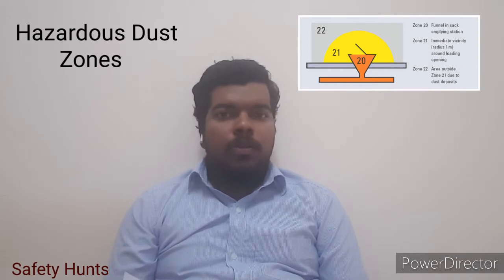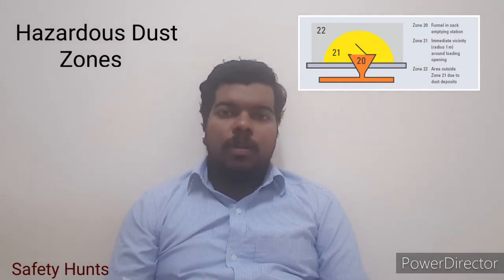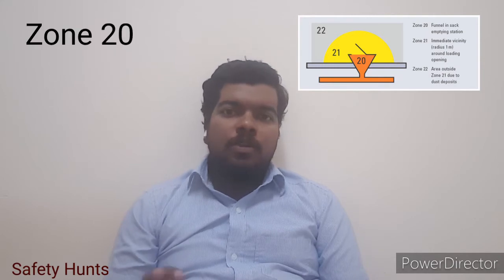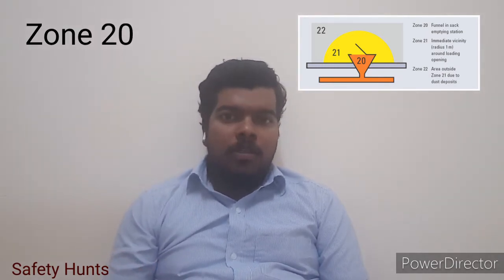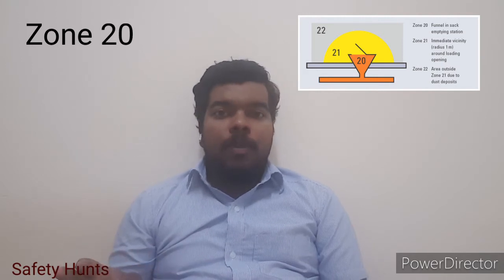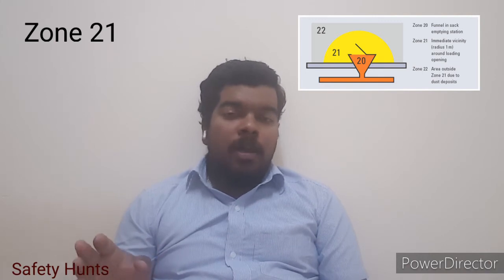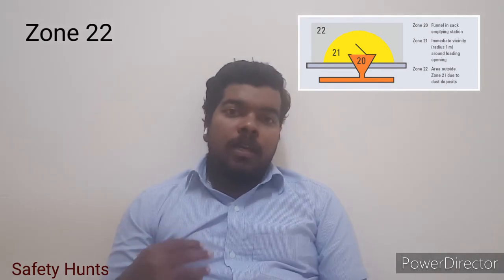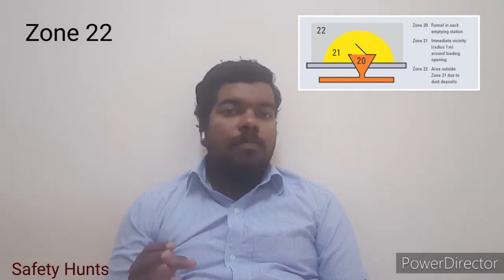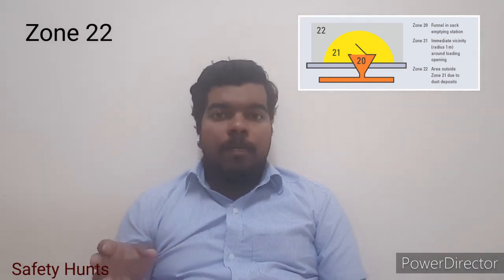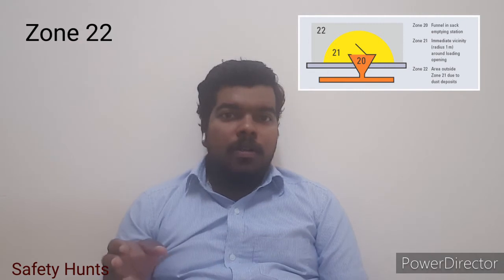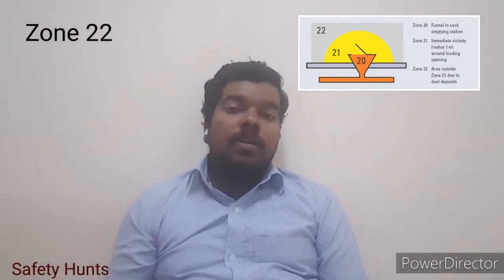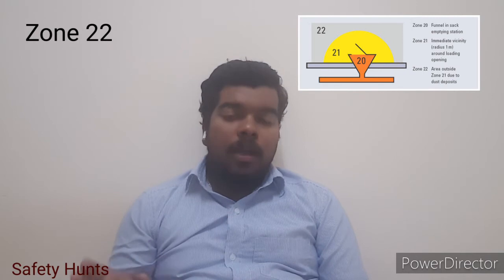Let's see what is hazardous dust area. Dust area is classified into Zone 20, Zone 21, and Zone 22. Zone 20 is a presence of flammable and explosive dust for a continuous period of time. Zone 21 is where flammable and combustible dust may likely be present. Zone 22 is an area where, under normal operation condition, the presence of flammable and combustible dust will not be there, but if there is any maintenance or operation maintenance going on, there will definitely be a presence of flammable and combustible dust.